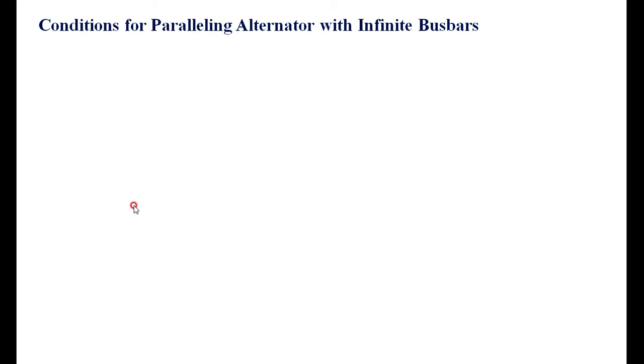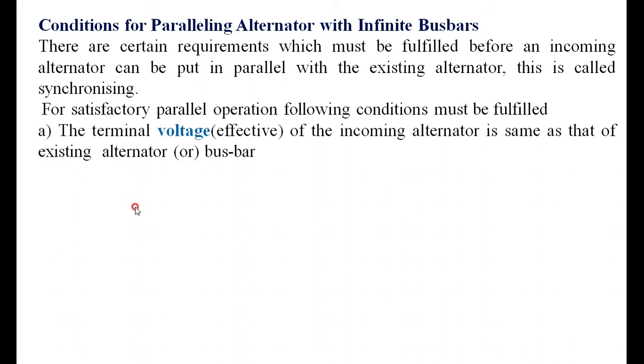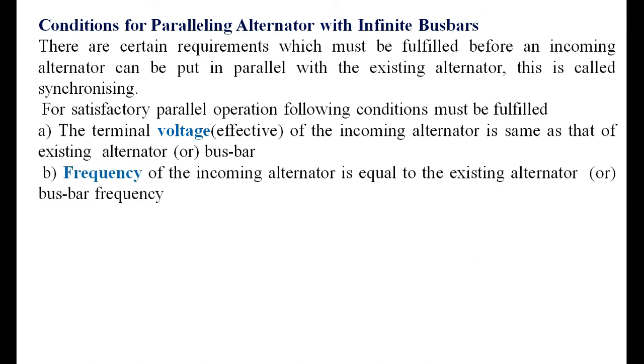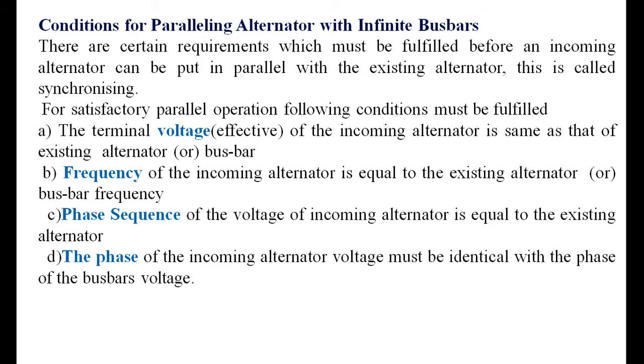We know the conditions for parallel operation: first, the terminal voltage of the incoming alternator must be the same as the existing alternator; second, the frequency must match; third, the phase sequence of the incoming alternator must be equal to the existing alternator on the bus bar; and fourth, the phase of the incoming alternator voltage must be identical with the phase of the bus bar voltage.